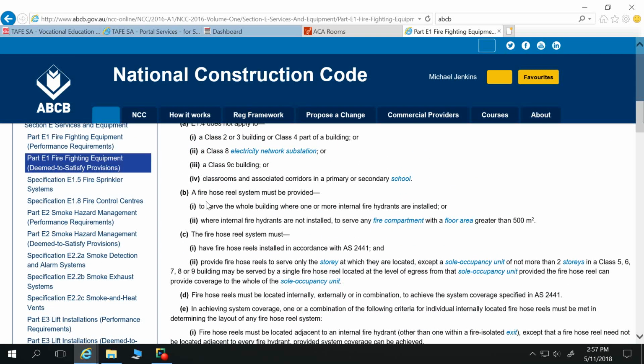A fire hose reel system must be provided to serve the whole building where one or more internal fire hydrants are installed. Okay, so we have to have fire hydrants, right? So now, because we've got fire hydrants, we have to have fire hose reels. That's what that tells us. Or number 2, where internal fire hydrants are not installed, to serve any fire compartment with a floor area greater than 500 square metres. So we don't have a choice about that. So we have to have fire hose reel systems to serve the whole building where one or more internal fire hydrants are installed.